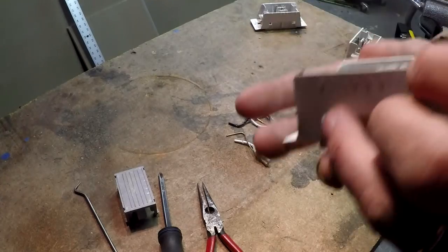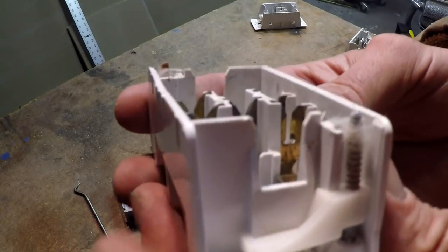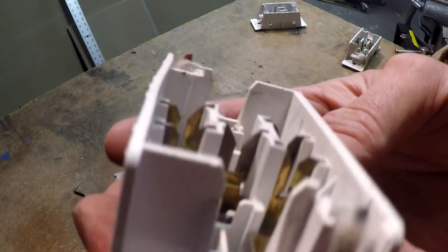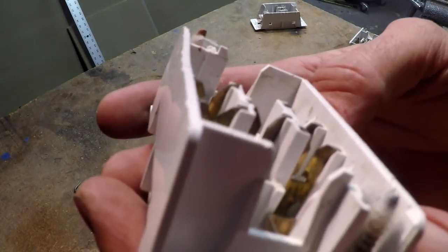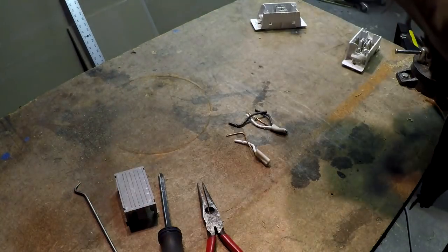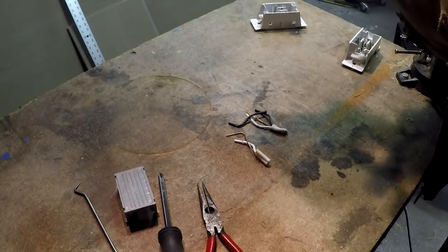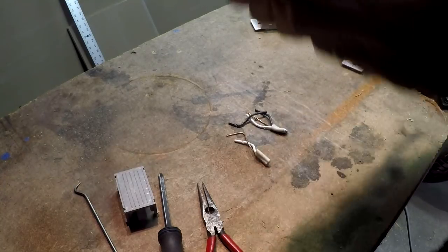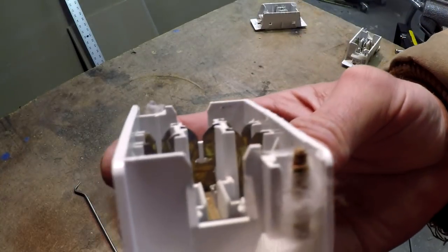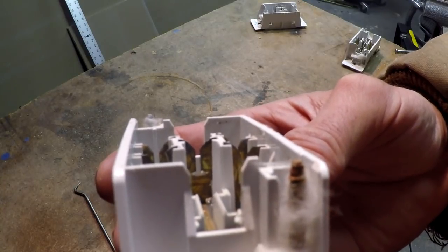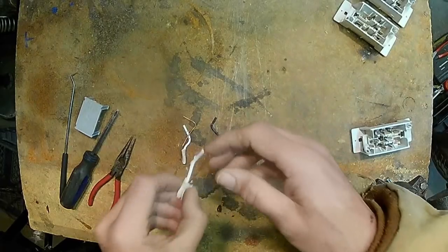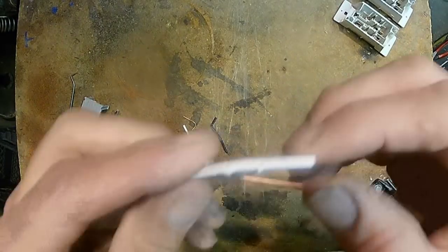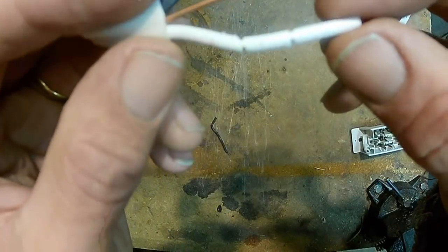Okay, now on this one, you'll actually see some basically tarnishing of the metal of the contacts. And generally what that shows is there's basically age, but also excessive loads placed on it. There it is there. See if I can get you a nice close-up.